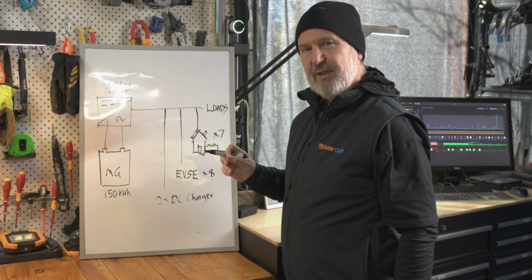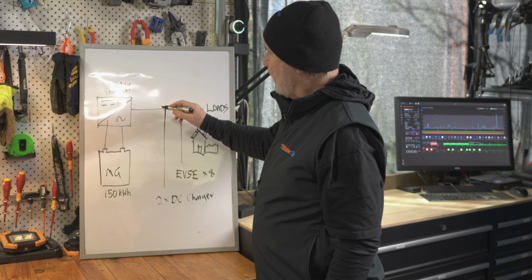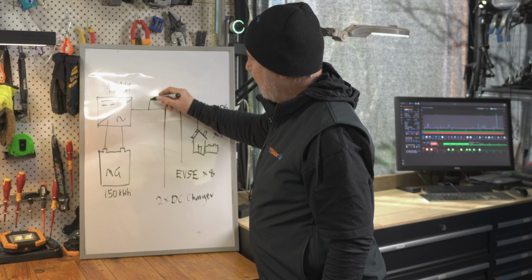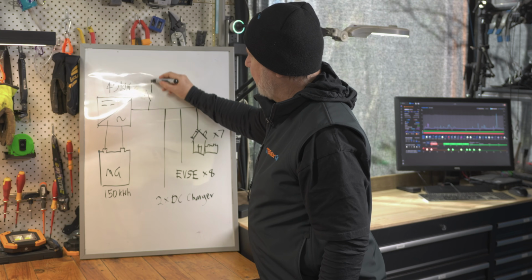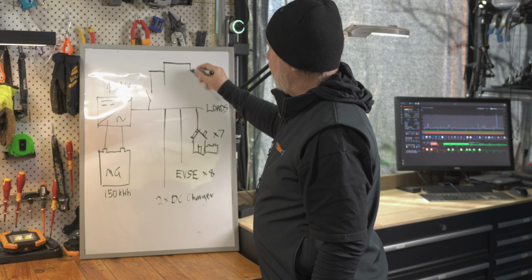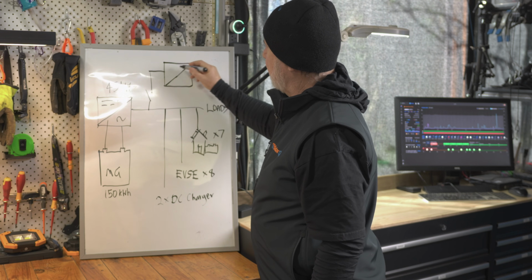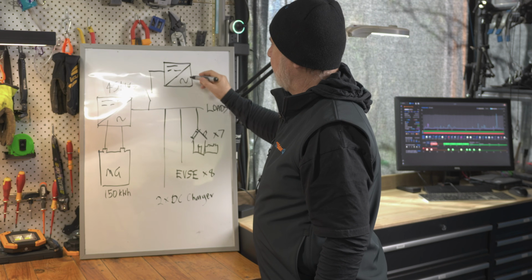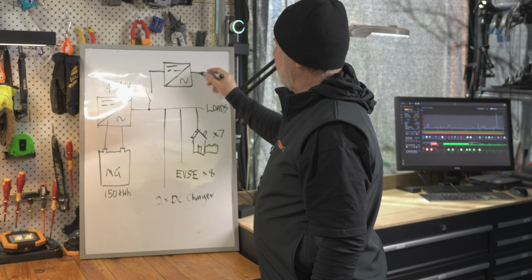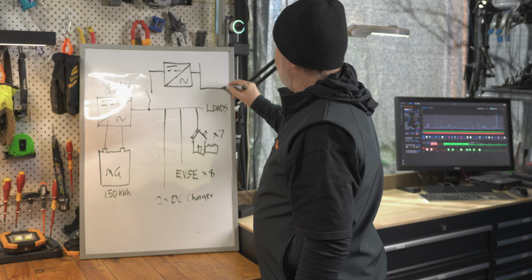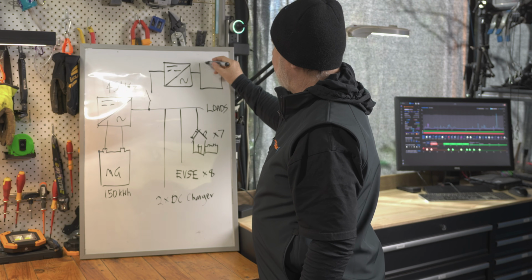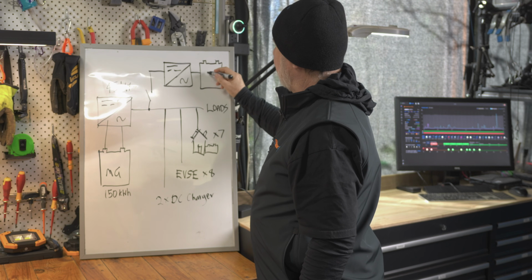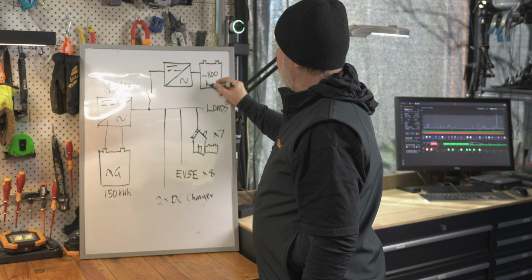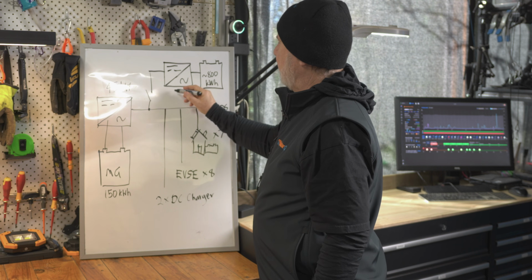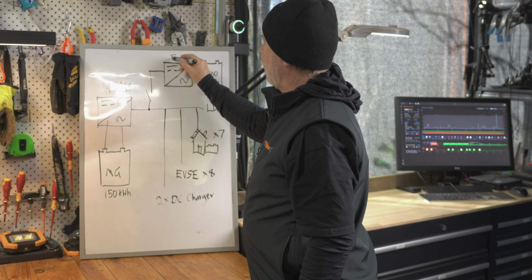So how did we add more capacity to this? Well, we did what's known as AC coupling. So we brought in, in parallel, the Solis 50 kilowatt hybrid inverter. And it's got its own big battery. As I said, it's potentially up to 800 kilowatt hours, so approximately 800. And this is rated at 50 kilowatts.